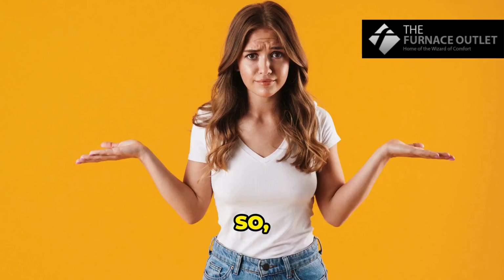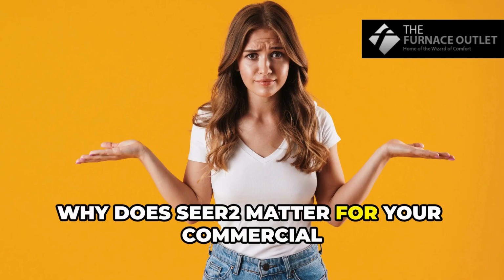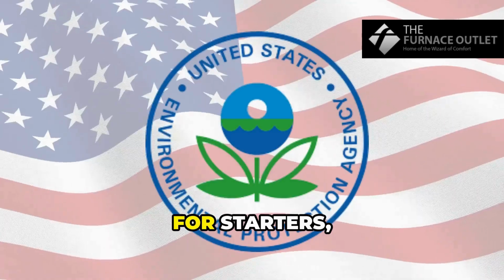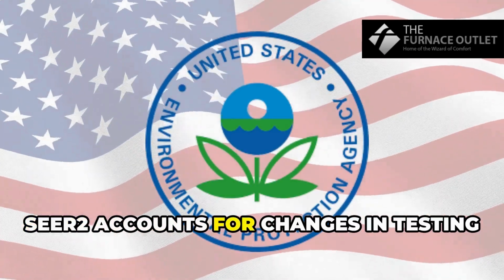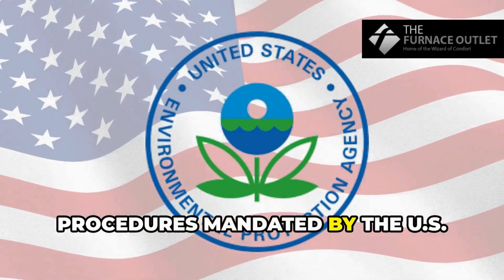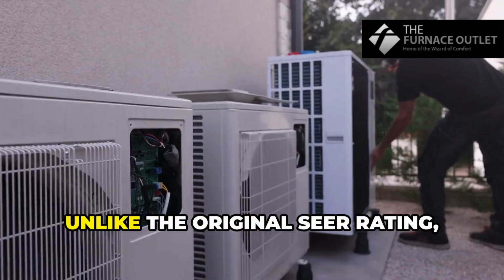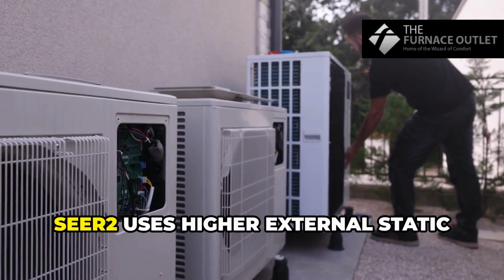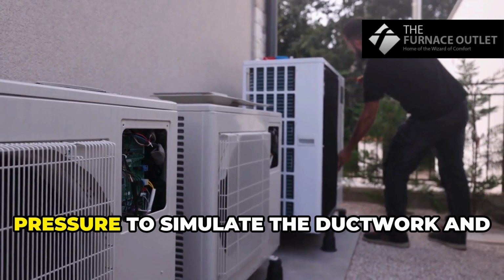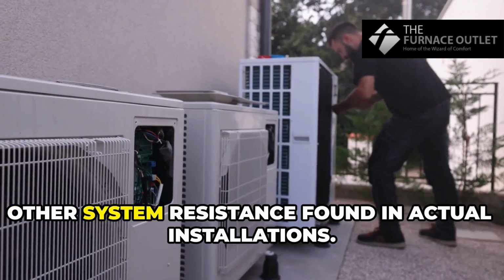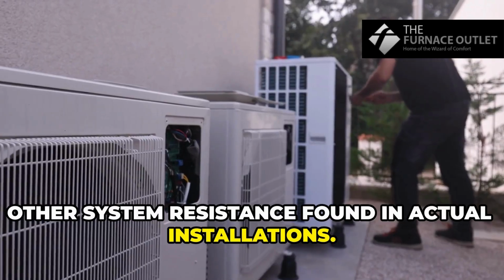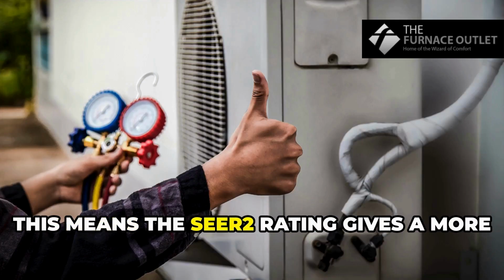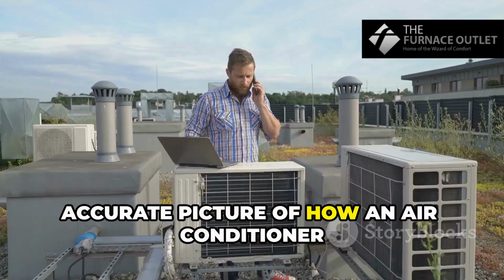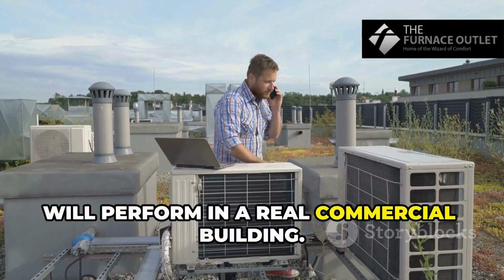So, why does SEER2 matter for your commercial HVAC system? For starters, SEER2 accounts for changes in testing procedures mandated by the US Department of Energy. Unlike the original SEER rating, SEER2 uses higher external static pressure to simulate the ductwork and other system resistance found in actual installations. This means the SEER2 rating gives a more accurate picture of how an air conditioner will perform in a real commercial building.